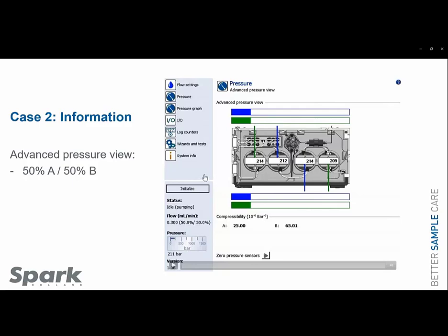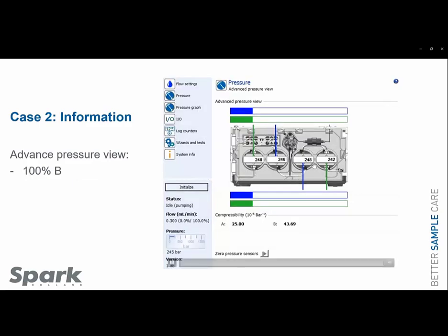Let's see what it's doing when we do 100% B. Loading fresh mobile phase. Let's see. It's a small stroke. 6 bar below system pressure. And this is good, giving a compressibility factor. So this is good. Pump B is good.